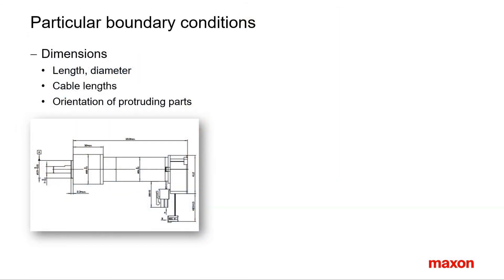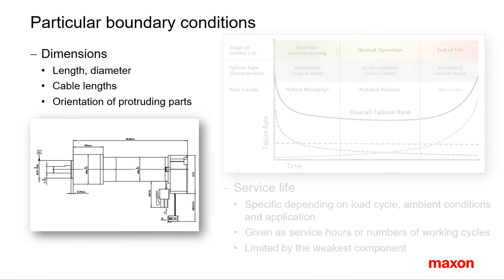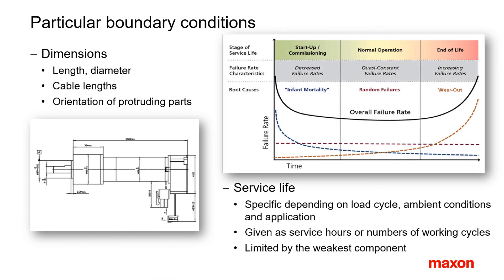Particular boundary and mounting conditions may strongly influence the type and costs of a drive. Usually, the maximum drive dimension defines also its maximum power and its price. The service life of drives cannot be calculated exactly — it strongly depends on load cycle, application, and ambient conditions. However, a service life estimation is possible by means of experience values from similar applications. The expected service life is usually given as service hours or number of working cycles.